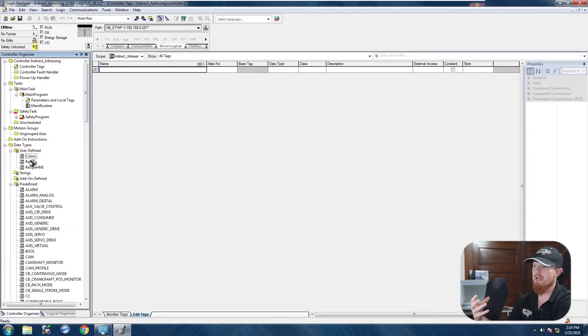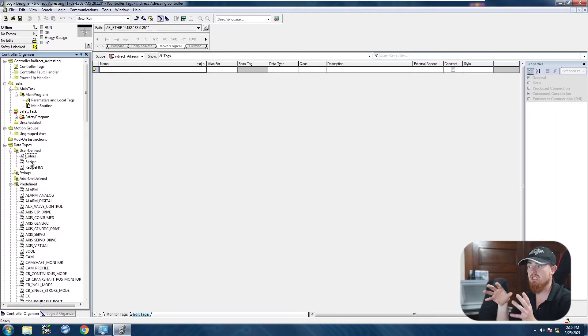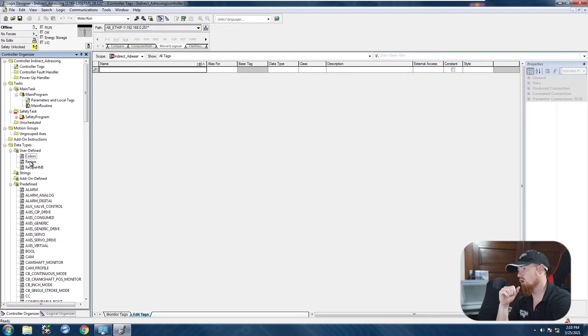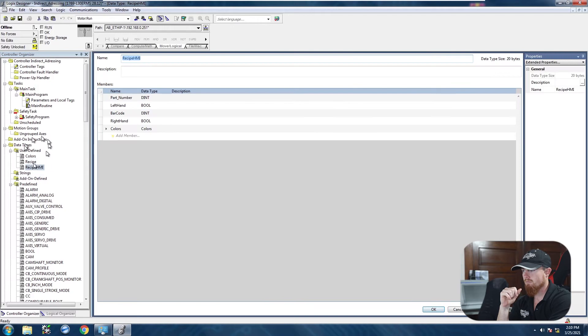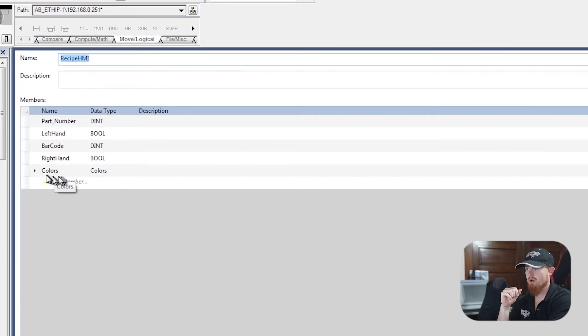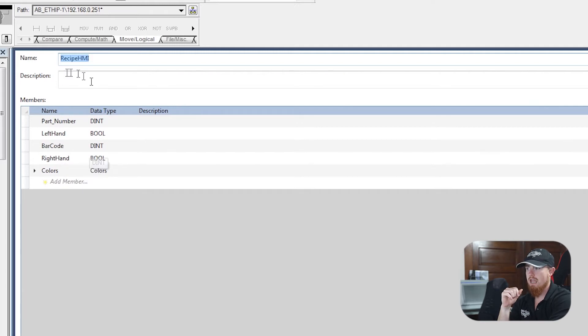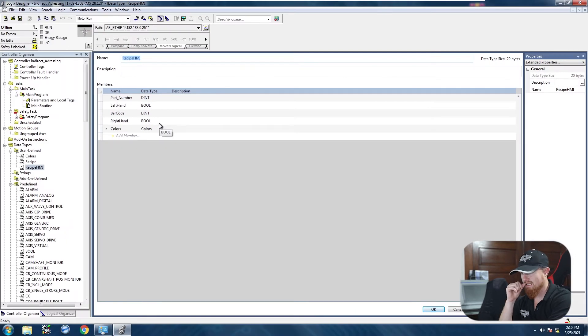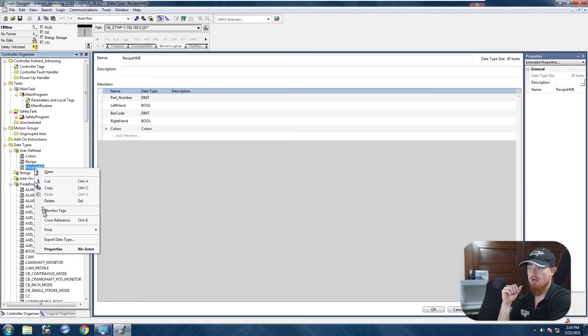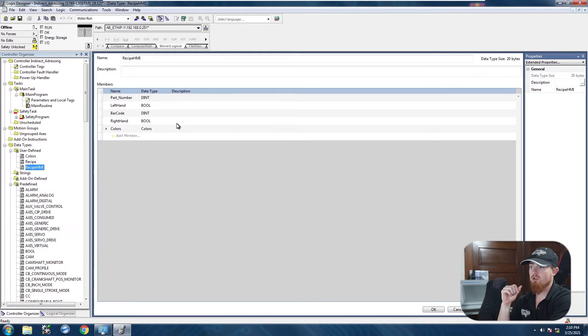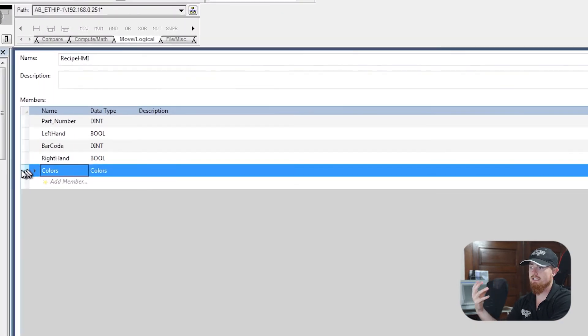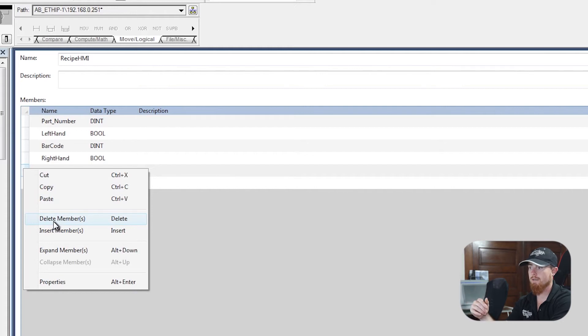And so you'll see this quite commonly where you want to have a UDT for like, say, for instance, cylinders, but then you want to put cylinders inside of your recipe. So here we're using a UDT inside of a UDT. So here is our colors data type, and here we are in our recipe HMI. So with that being said, you either got to do one or two things. You either got to delete the whole entire recipe HMI UDT, or you got to come over here and you got to delete the colors out of this UDT.